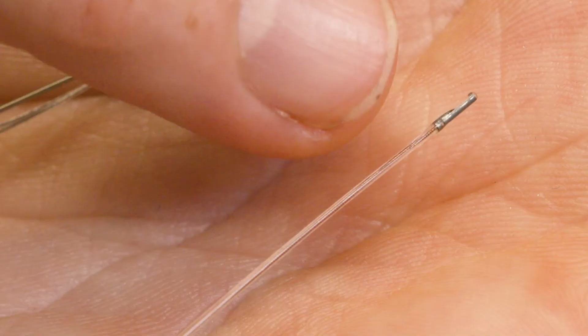The solid state aspect means that the pressure signal is transduced at the very tip of this. A traditional way to measure blood pressure is to use a fluid-filled catheter, where the pressure signal would have to be carried all the way along the catheter to the body of the telemeter, or outside the animal if it was a catheter running outside the animal. But that creates an opportunity for noise or movement artifact to get into that signal. So by picking up the signal and transducing it here, we're recording exactly what's happening. It's the most high resolution signal that you can currently get.